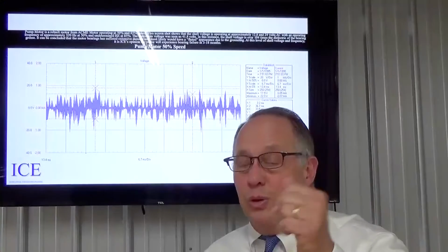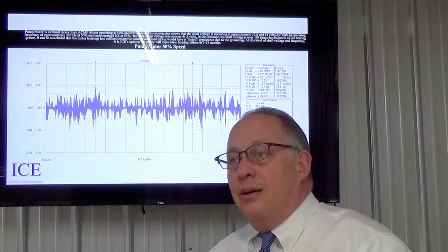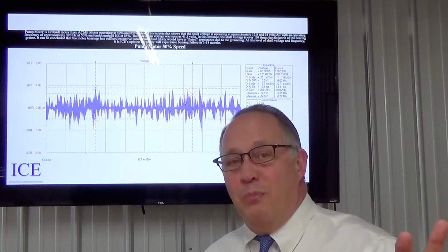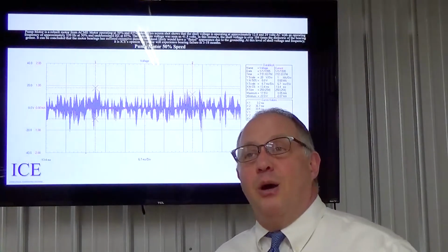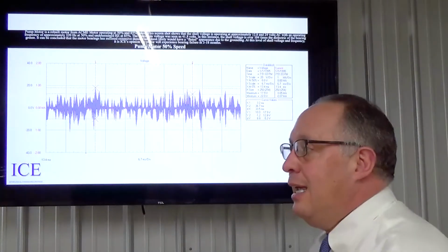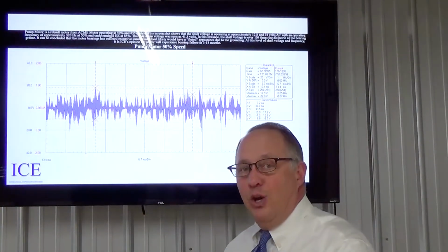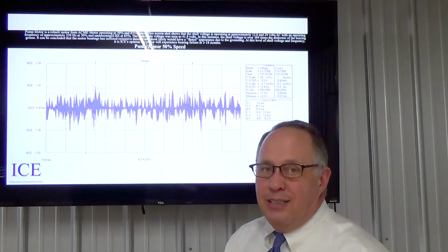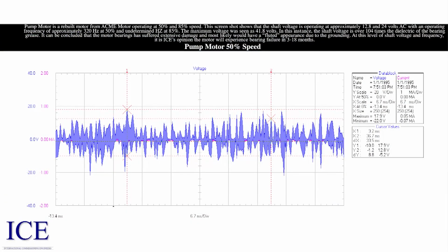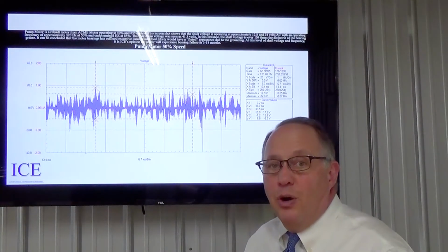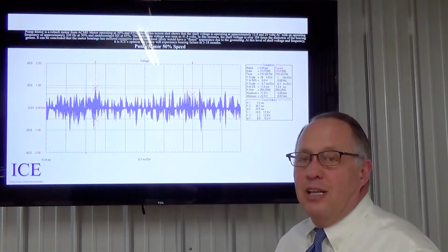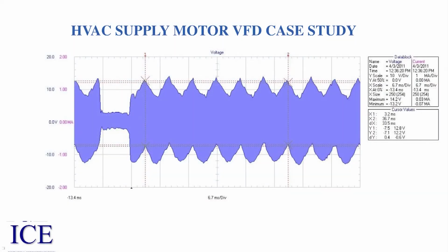The rebuilt motor was installed. We were called in after the one motor had already failed, and they ended up rebuilding the motor and putting it back in. So this is basically a new motor, and we're already getting these types of voltages. Once we installed the shaft voltage grounding rings, it dissipated to just a few, actually millivolts in that case, but essentially zero. Problem solved.